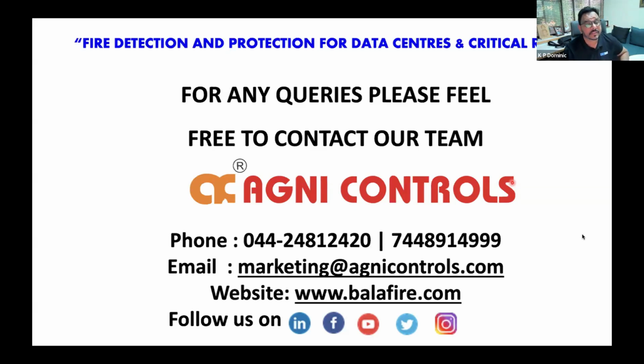So Arvind is asking, what is the maximum coverage angle for IR and UV detectors? Can it fit in the conference hall in the corner? It depends on the size of the conference hall also. The coverage is a 90-degree cone angle, which means 45 degrees to the left, 45 degrees to the right, 45 degrees to the top, and 45 degrees to the bottom. So it forms a cone of angle similar to our eye vision. When we put it in the corner of the room, it will cover almost 80% of the room, and maybe only the area underneath the detector will not be covered.